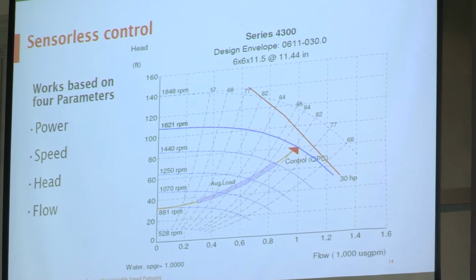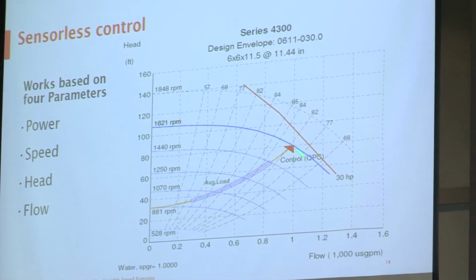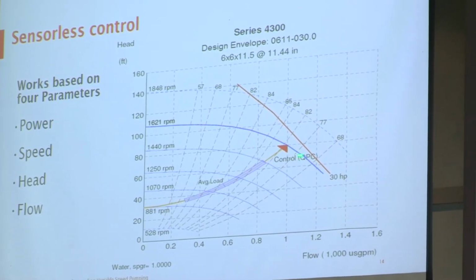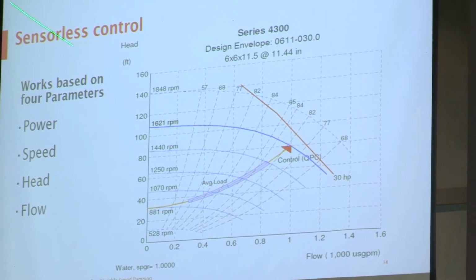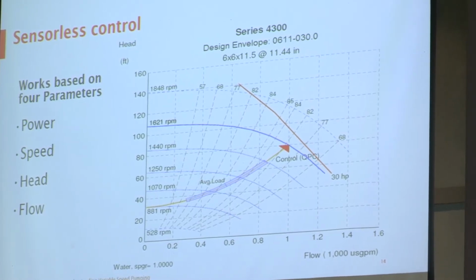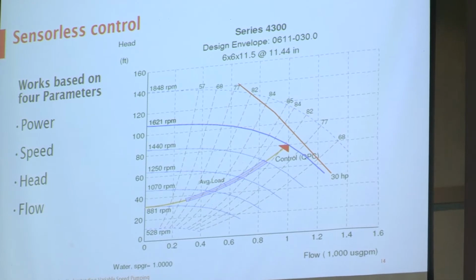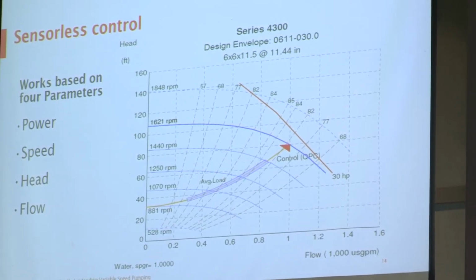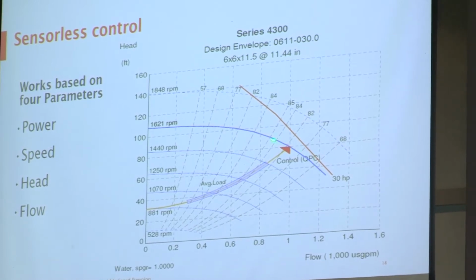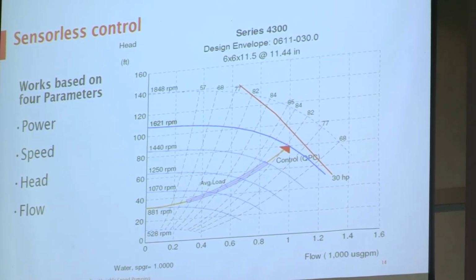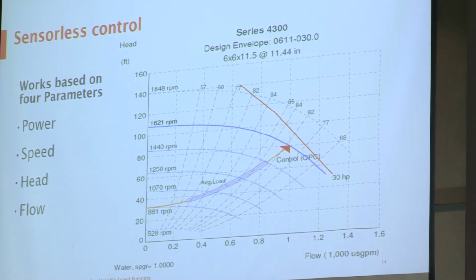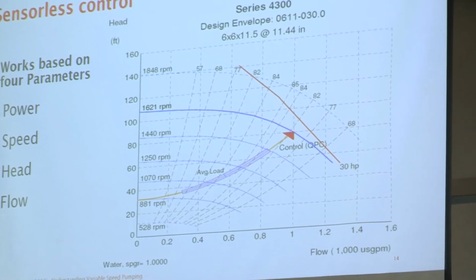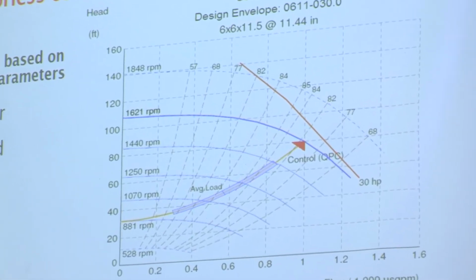With sensorless control, when I'm operating at this point and a valve starts closing, my work or my brake horsepower starts to change. And the end result is that I see a change in the amount of work I'm doing, and I adjust accordingly to get back to the control curve. That's the concept or the technology behind it. So how's it done?